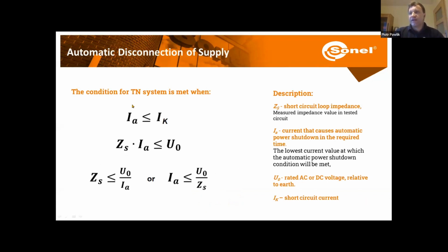Okay, so right now we have the current triggering our breakers in a desired time, and the fault current which is flowing into our circuit in case of a fault situation. So we need to compare the two, and if the fault current is higher than the current triggering the breaker, that means that the evaluation of our network will be positive. Now in the IS732, you can find all these three equations.